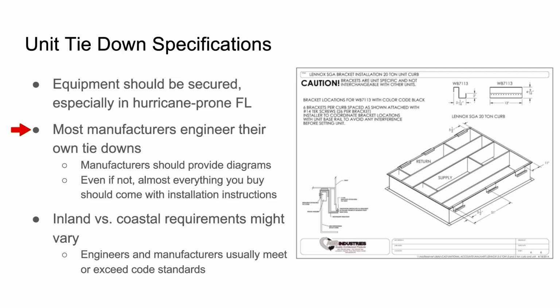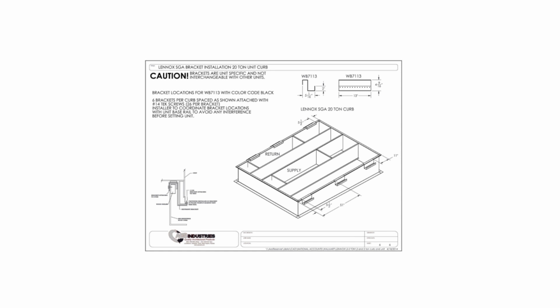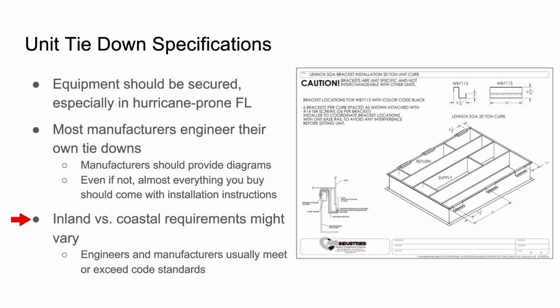Most manufacturers actually engineer their own tie-downs, and you can request that. This is a sample of a clip tie-down method for Lennox. We get the correct tie-down brackets and attach them by the measurements and means they request, typically a number 14 screw, small but visible. The old style has roughly 15 3/8 lags on the inside and 15 on the outside. Newer ones use more brackets, but only 4 on the inside and 4 on the outside.